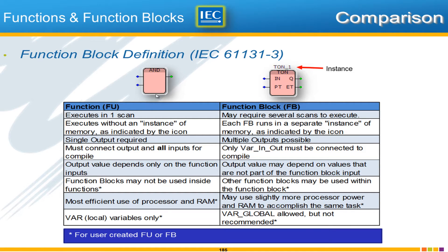Because of this difference, a function does not have what we call an instance, which is the title above a function block. A function operates and if there's another function next to it, it operates in the same way immediately. Whereas a function block has to store all of its operational results into memory for the next scan — that's called an instance. One telltale sign of whether it's a function or function block: look for this title. There must be an instance of the function block; there will never be an instance of a function.